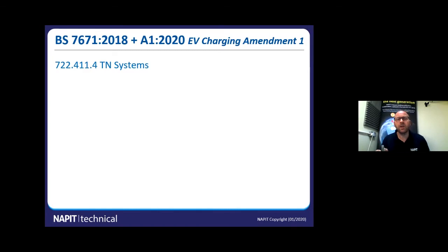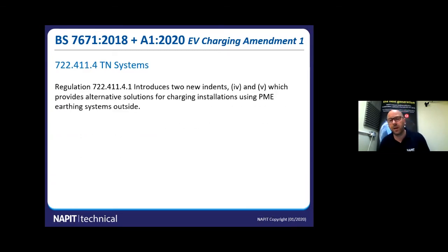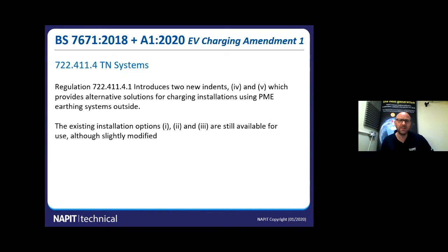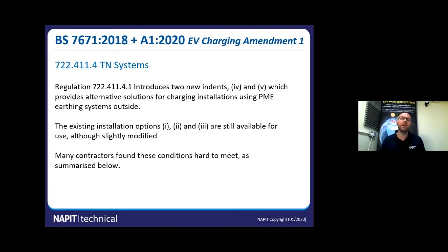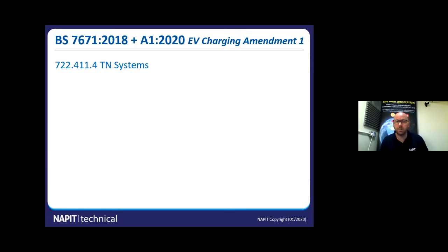Okay, so the next big topic is with regards to PME earthing systems. So Regulation 722.411.4.1 introduces two new indents, 4 and 5, which provide alternative solutions for charging installations using PME earthing systems when you're charging outside. The existing installation options 1, 2 and 3 are still available. They've been slightly modified, but the principles are the same. Many contractors doing EV charging found those conditions hard to meet, as summarised below.